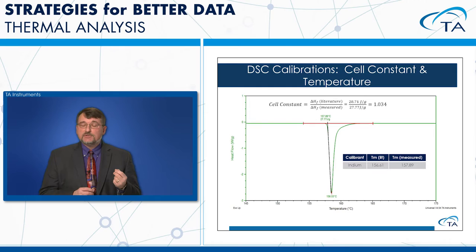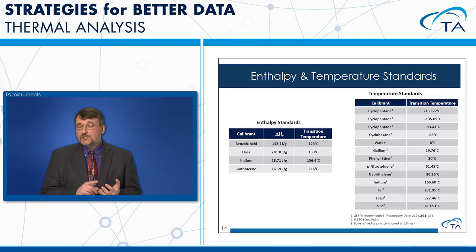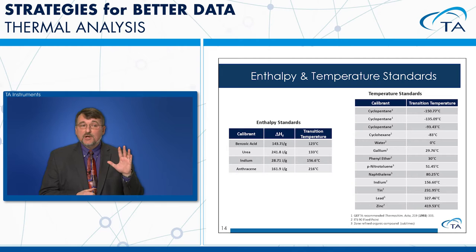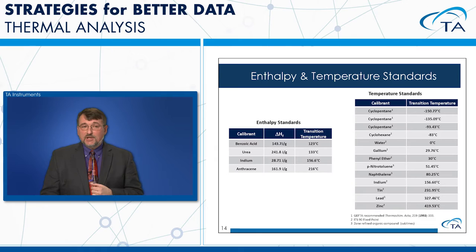You don't have to use indium — benzoic acid and urea are also common options, though indium is the most popular for cell constant calibration. For temperature calibration, up to five points can be used. We typically use metal standards like indium, tin, lead, or zinc, though many other materials are available as shown on the slide.